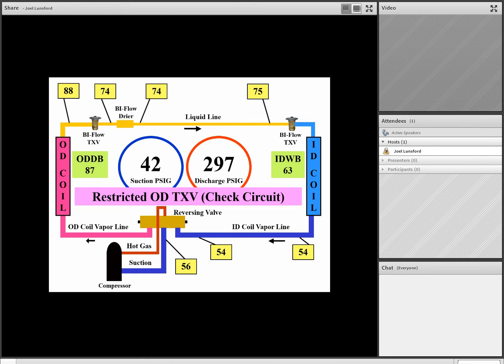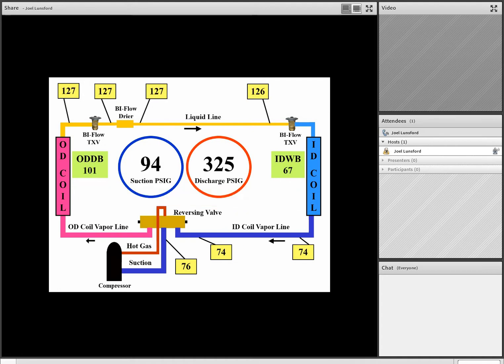Let's do another service call. In this example, we see we have an R22 call, and it's 94 pounds of suction pressure. Now, it is a hot day outside. It's 101 degrees outside with a 67-degree indoor wet bulb. So as we take a look at this service call together, we see that we have a 94-pound suction pressure, which is pretty high for an R22 system.